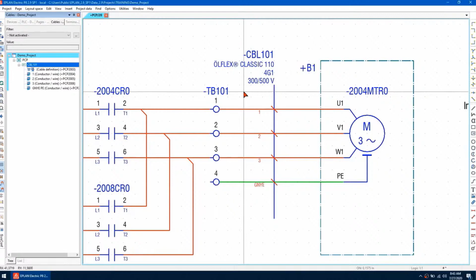So why is this? If we look at the terminal strip this cable is connected to, it goes 1 through 4 in the numbering scheme, but let's take a closer look. The order actually goes 1, 3, 2, then 4. Let's correct that by right clicking and going to edit, and sorting the terminal strip based on numeric values, then hitting apply. Now to update the cable, we go to the cable navigator, right click on our cable, go to assign cable connections, and reassign all. Once we do this, we get the correct sequence of conductors.